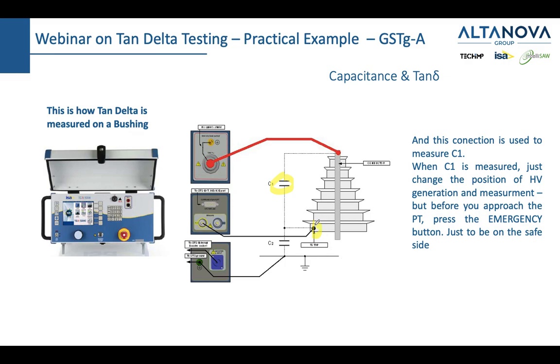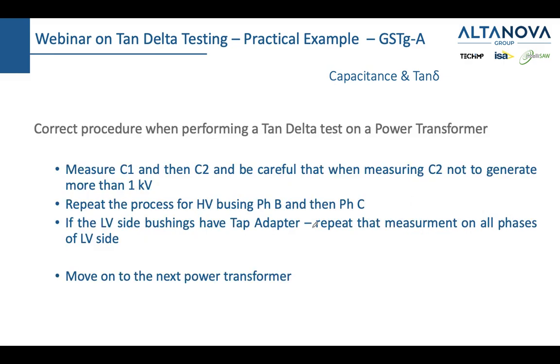And when you measure C2, please be careful so that you do not generate more than 1 kilovolt. In some cases, you can even go up to 2 kilovolts, but you don't need such a high number, and you are risking damage to the insulation or to the transformer if you generate a voltage which is more than 1 to 2 kilovolts while generating on C2.